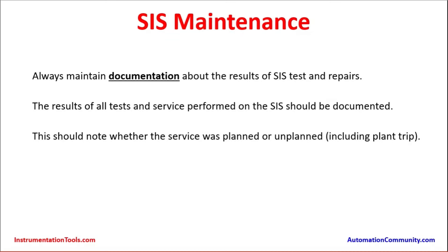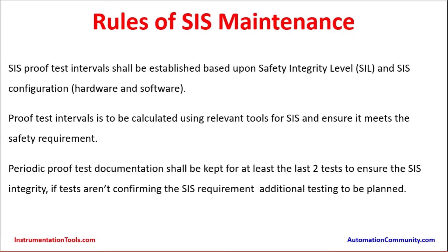For example, there may be a planned shutdown on 20th November for proof testing of a particular sensor and final element, but an unplanned trip happened around the 10th or 15th of November — a week before the actual proof test date. During this shutdown, the Safety Instrumented System would have acted, and the shutdown time can be utilized to do the proof testing on those instruments.